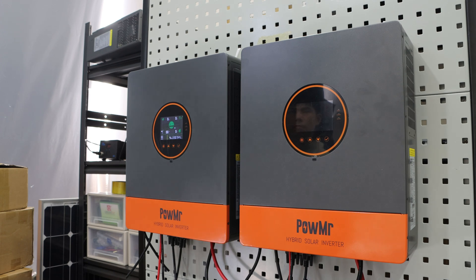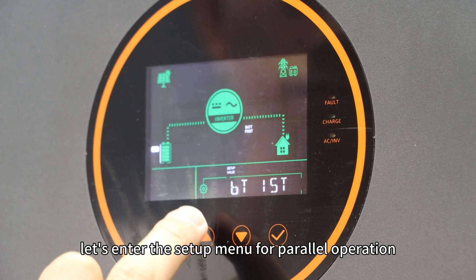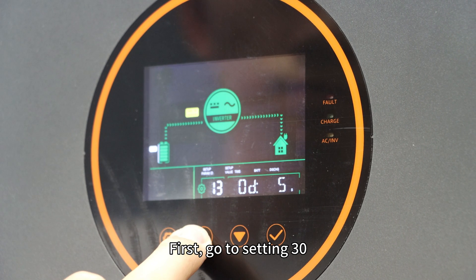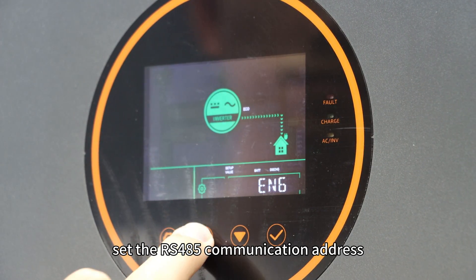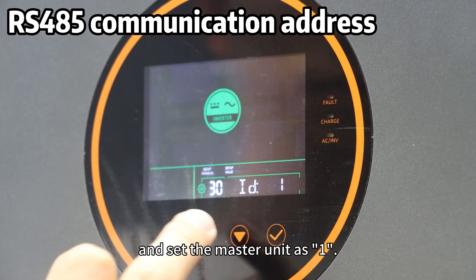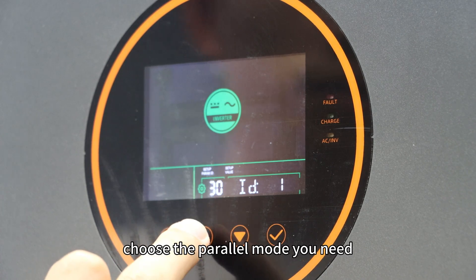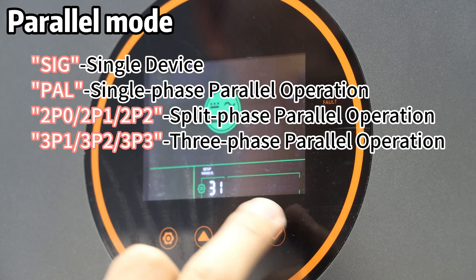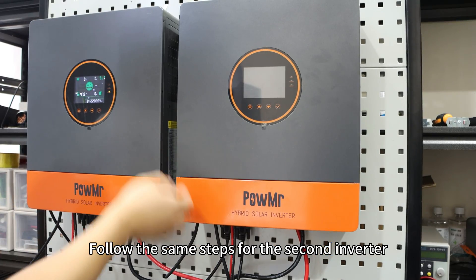At this point, the interface may display a fault, but no worries. Let's enter the setup menu for parallel operation. First, go to setting 30, set the RS-485 communication address, and set the master unit as 1. Then go to setting 31, choose the parallel mode you need. In our case, we are using split-phase configuration, so we select 2P0. Follow the same steps for the second inverter.